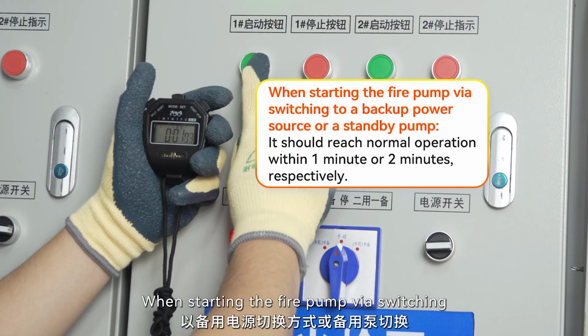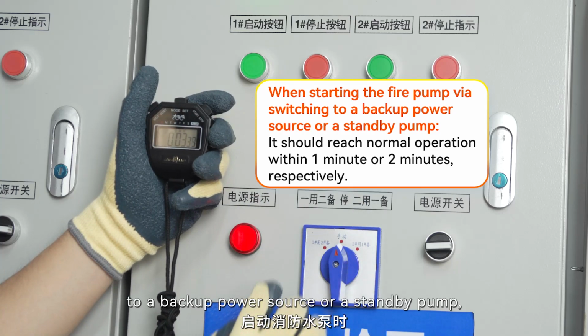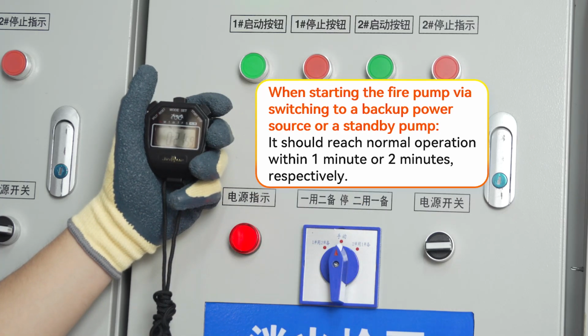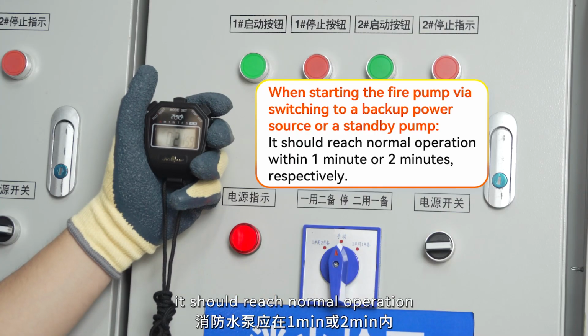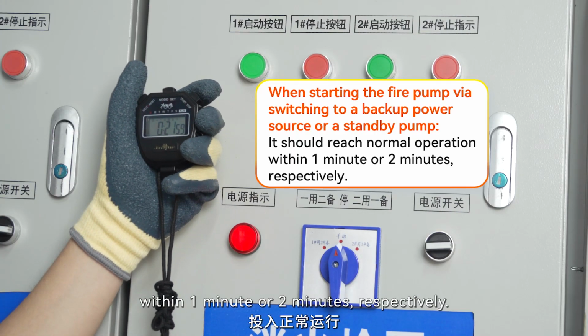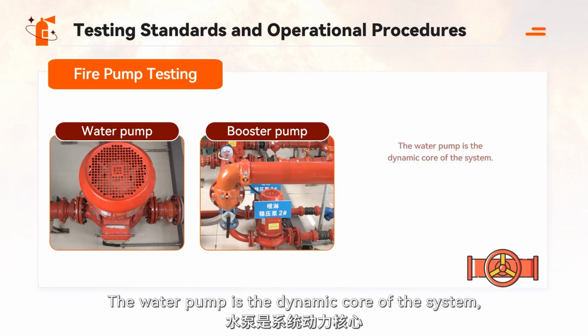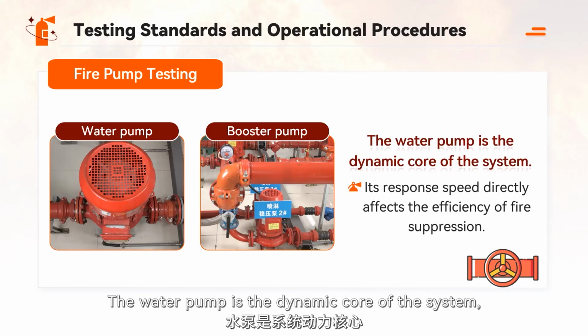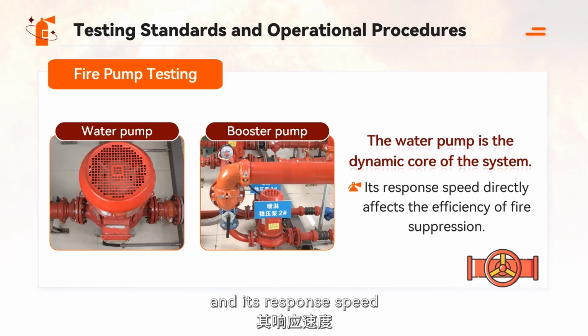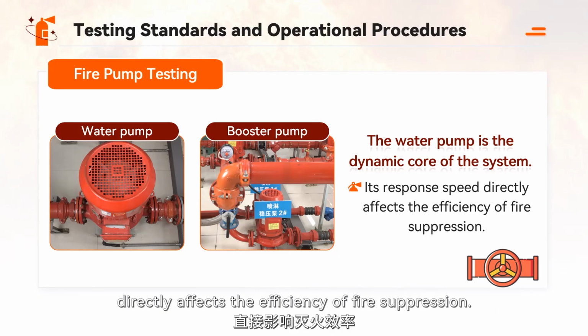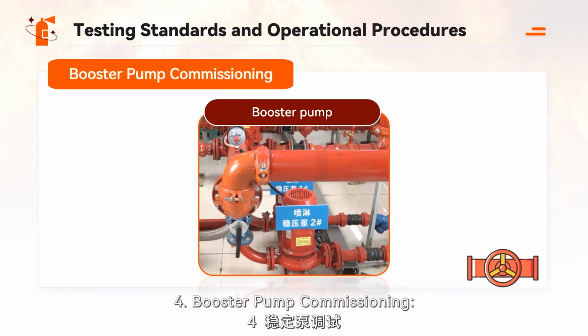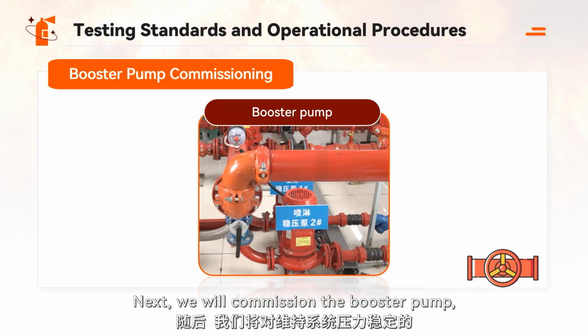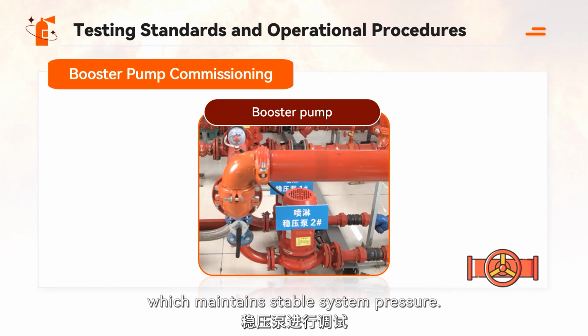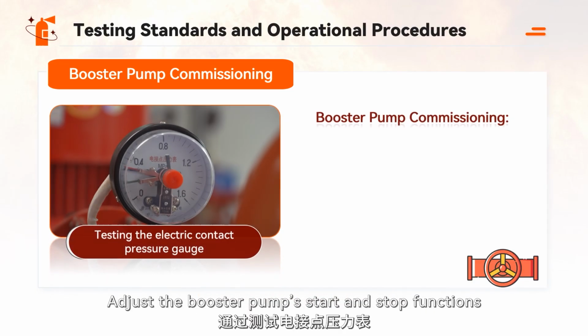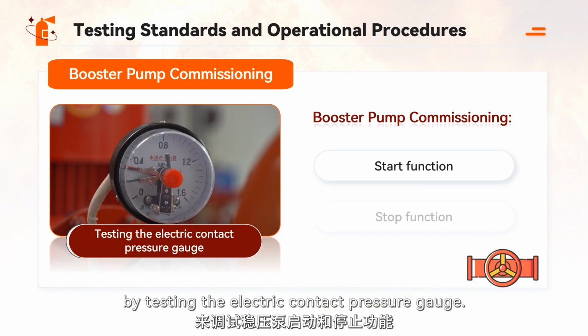When starting the fire pump via switching to a backup power source or a standby pump, it should reach normal operation within 1 minute or 2 minutes, respectively. The water pump is the dynamic core of the system, and its response speed directly affects the efficiency of fire suppression. 4. Booster pump commissioning. Next, we will commission the booster pump, which maintains stable system pressure. Adjust the booster pump start and stop functions by testing the electric contact pressure gauge.